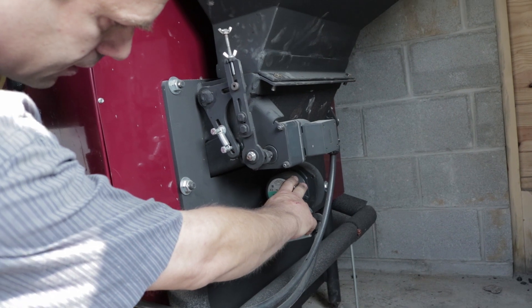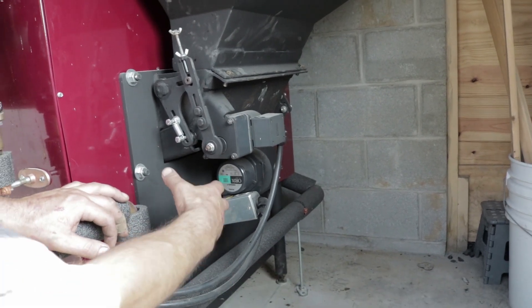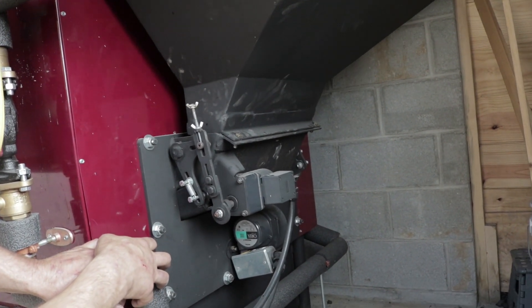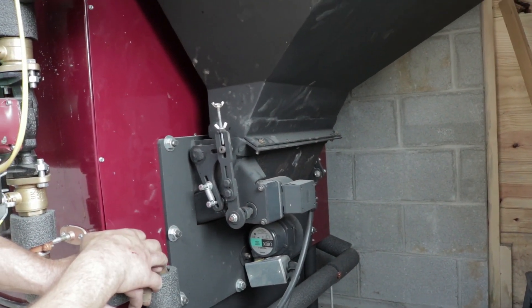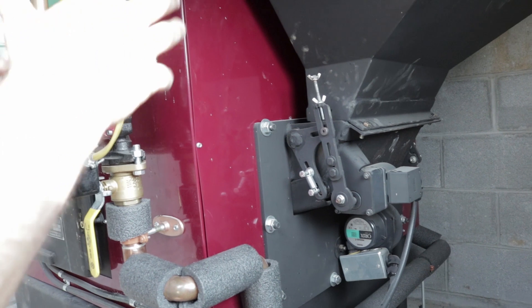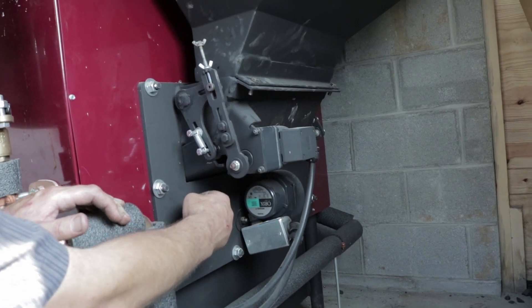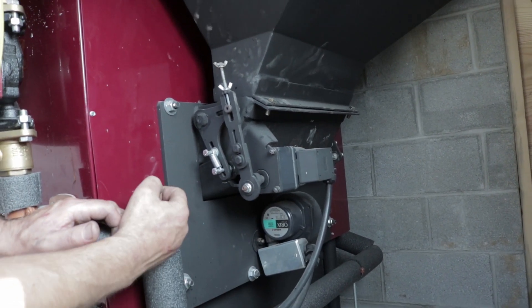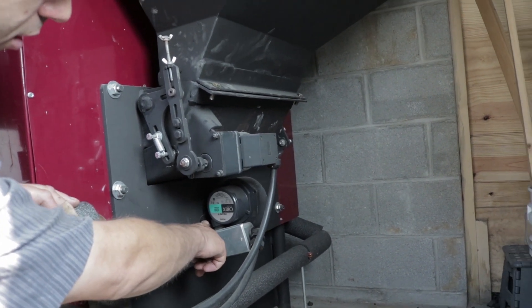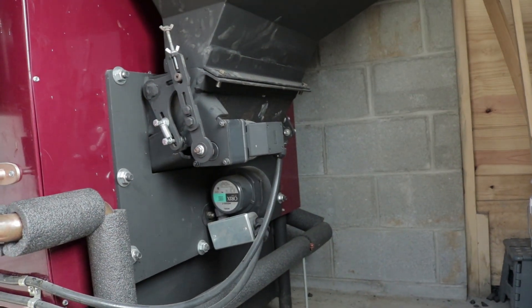Here is the primary air blower — combustion air blower — that provides the combustion air for the fire. This whole mechanism can be unbolted for installation if you need to move it through a doorway or down stairs — you can remove it so you just have the boiler vessel itself. The air fan and air chamber are easily accessible: remove a mounting nut on each side and you can pop the fan off and clean it out very easily.